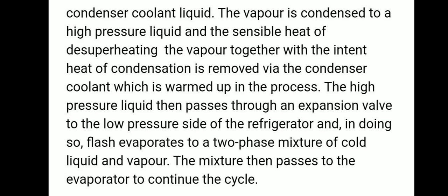So here the vapor is condensed to a high pressure liquid, and the sensible heat of desuperheating together with the latent heat of condensation is removed via the condenser coolant, which is warmed up in the process. The high pressure liquid then passes through the expansion valve to the low pressure side of the refrigeration system. In doing so, it flash evaporates to a two-phase mixture of cold liquid and vapor. The mixture then passes to the evaporator to continue the cycle.